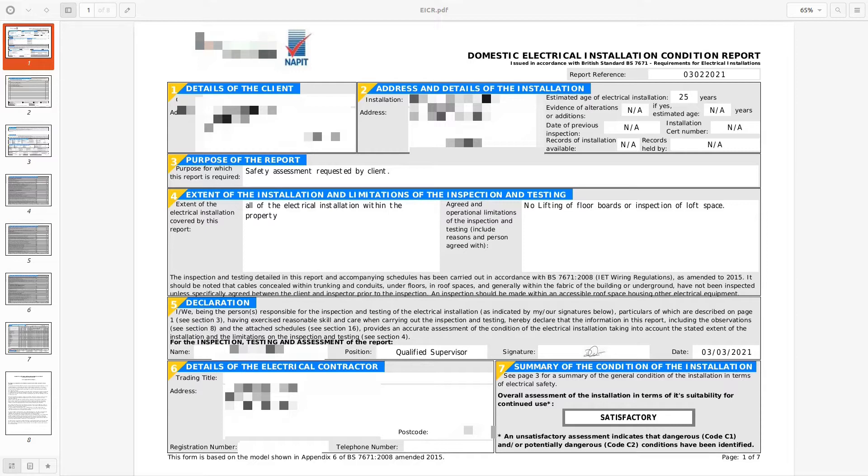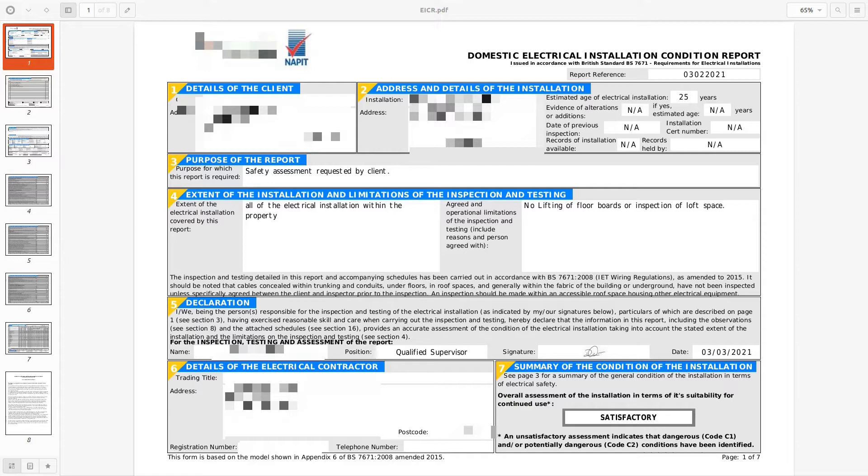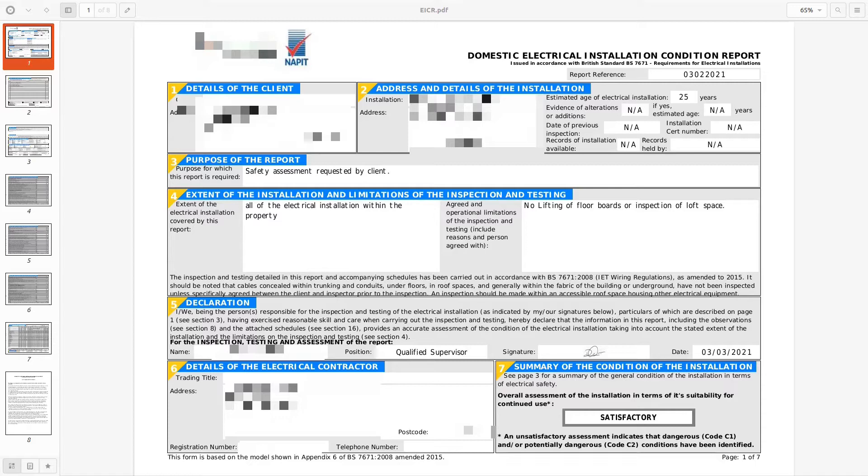The purpose of the report was for a safety assessment requested by the client. The real reason is it's a landlord and requires the certificate to be completed and up to date for the purposes of rental. That would probably be a better reason to put into that box for continued safe service for rental purposes or towards of that effect.